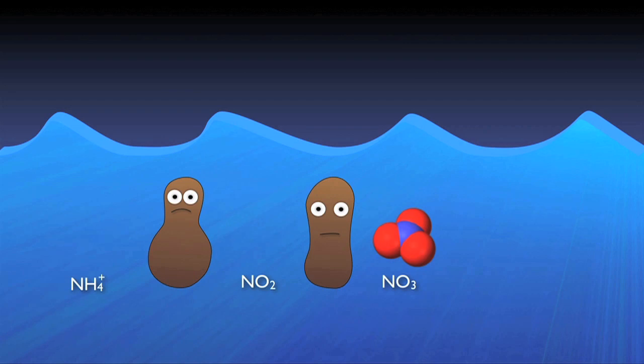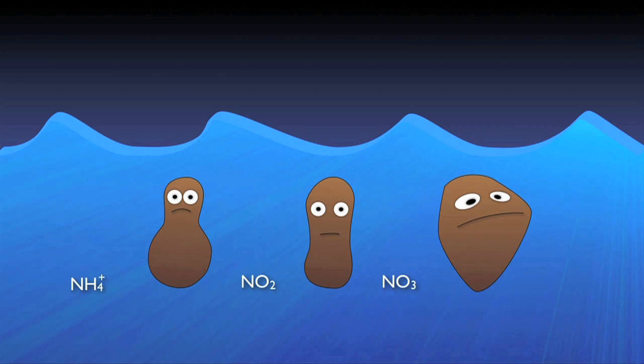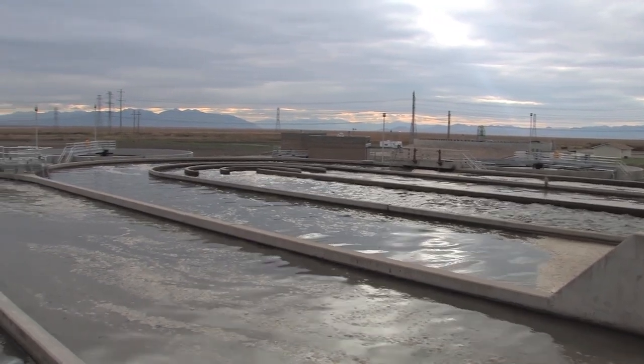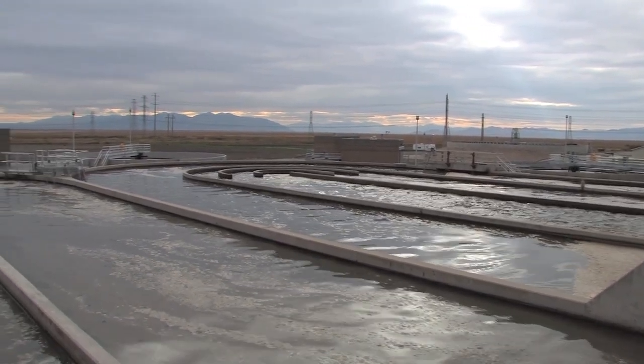As dissolved oxygen is depleted by the nitrifiers and other organisms in the basin, other specialized heterotrophic bacteria — denitrifiers — are able to thrive by using the oxygen attached to the nitrate molecules for respiration, creating nitrogen gas as a byproduct. The nitrogen gas then simply bubbles out of the water into the atmosphere. Let's go back to the beginning and take a closer look at each of these important steps in the nitrogen removal process.